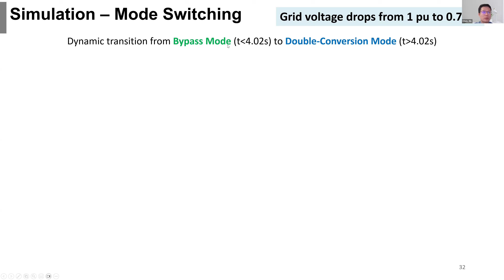Let me show you some simulation results using our model. So for this AI data center model, if we simulate a grid side voltage drop from 1 per unit to 0.7 per unit, the system will transition from the bypass mode to the double conversion mode. And here are the simulation results. So we can first look at the left figure. This is the simulation results when the grid side voltage drops to 0.7 per unit.